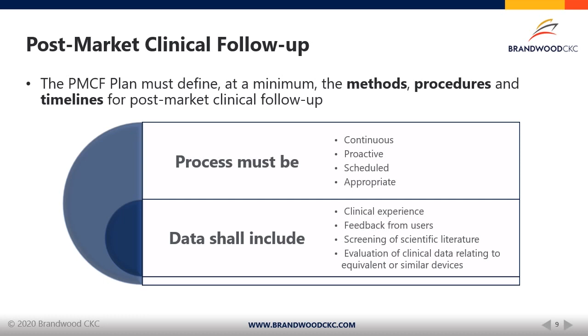So we've covered what needs to be included in the planning stage, but let's now look at the sorts of post-market surveillance activities that provide the required outputs. So the PMS activities, as I've got written here on this slide, will include things like vigilance processes. So information on serious incidents, including information from periodic safety update reports and field safety corrective actions. An activity such as trending will provide you with trend reports, for example, trending of parts replaced in medical device servicing activities.